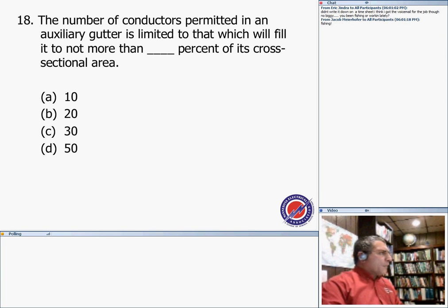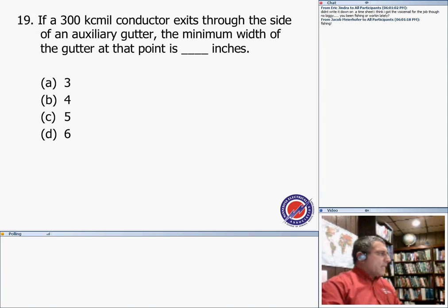18. The number of conductors permitted in an auxiliary gutter is limited to that which will fill it to which point? Number 18, our answer is 20%. So if you have a gutter, you treat it almost like a conduit and do not fill more than 20% of it. Is everybody right on that? This is one where some of you guys got it wrong.